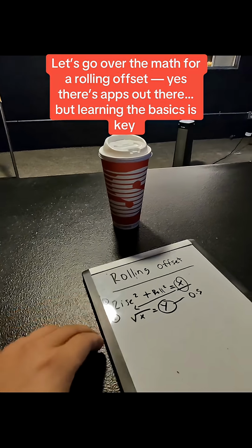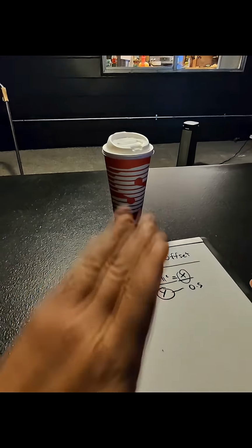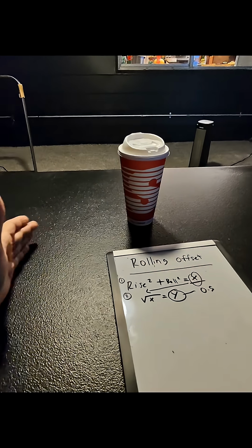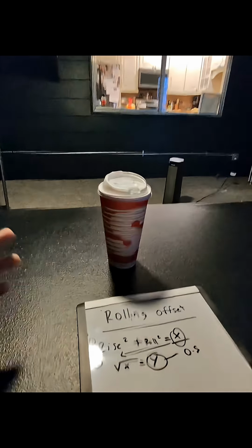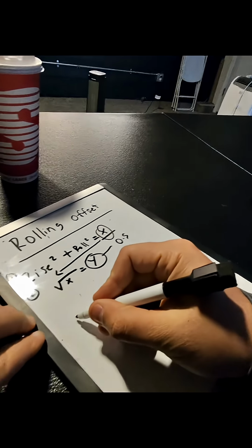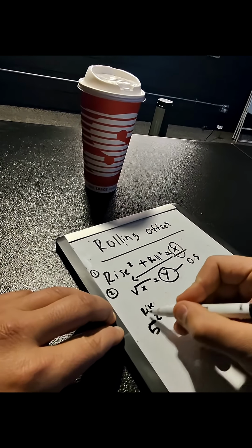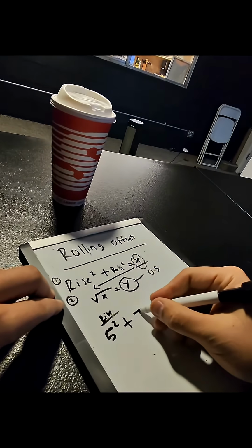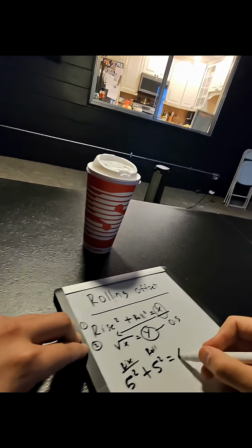forth. Let's assume that we have a 5-inch rise, so an elevation change, but we also need to roll our conduit to get 2 inches center to center beside a conduit that's already ran. Let's assume the roll needs to be 5 inches as well. Make it very simplistic. So rise, we said, was 5 inches, so we're going to take 5 squared, which is our rise. We're going to add that to our roll, which we said needed to be a 5-inch roll. We're going to also square that. This is our roll. And from that, we're going to get x squared.